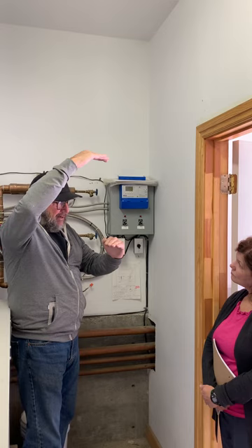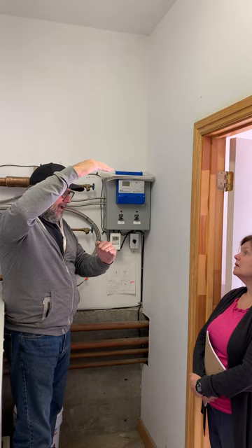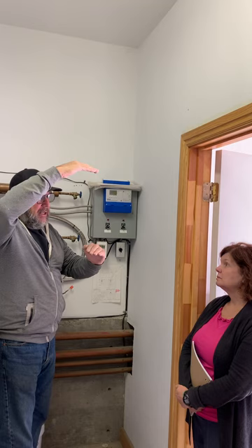Up in Park City, we kind of have to lower that temperature. And I've got doctors and people that have to have their driveways melted all the time. And you've got to lower that down, whatever it is, you've got to pay the bill. But it costs you double to melt snow at 0 degrees as it does at 20 degrees. That's what that's there for.